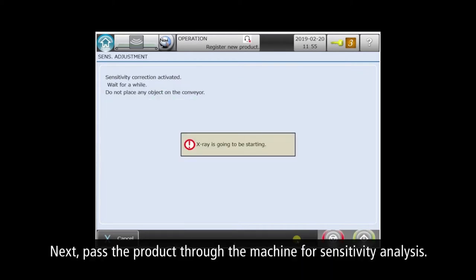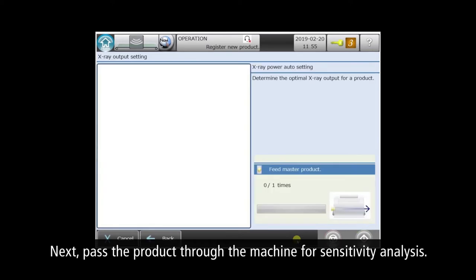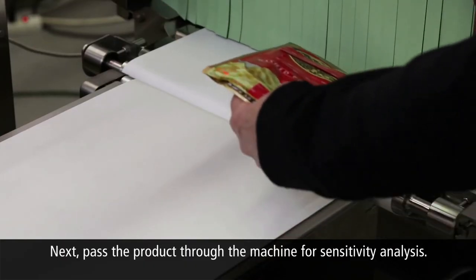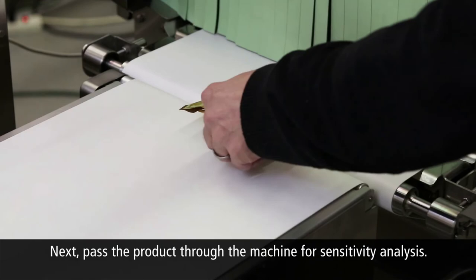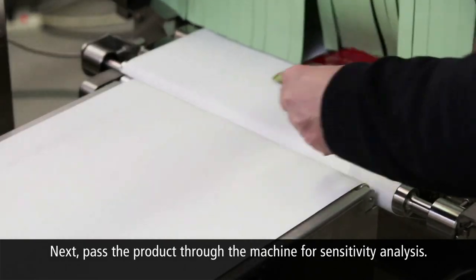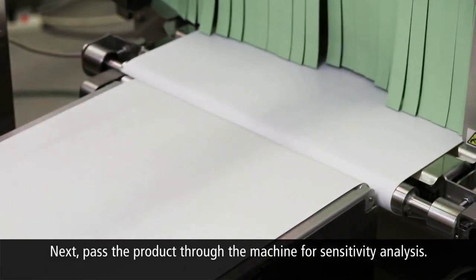Next, the wizard prepares for a single master product pass-through to calibrate sensitivity and power. The wizard analyzes the X-ray data and then advances to the next step. Here you can see the appropriate X-ray output settings for best sensitivity with this product.